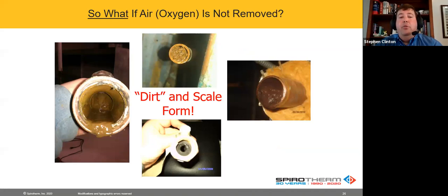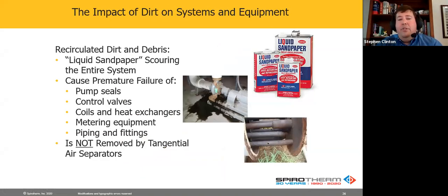Why should we care? Well, some of these slides may look familiar to some of you. Dirt and all the junk that happens with it. Some of it's biological, some of it's truly dirt that's got into the system. But oftentimes when you say the term dirt, that is fine metallic debris. It's basically rusty material. What's happening when that's flowing through a system? It's essentially liquid sandpaper. It's small metallic debris zipping along at 10 feet per second.